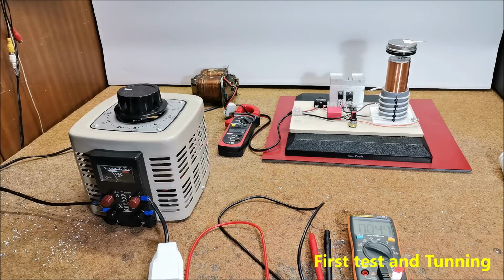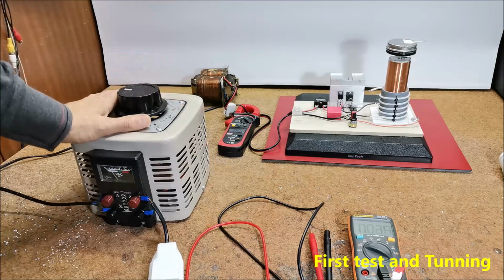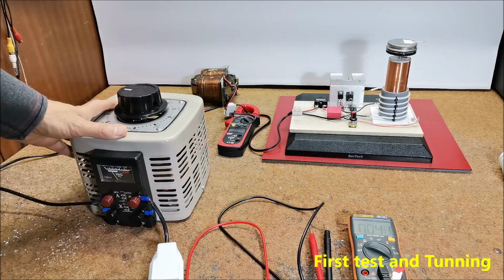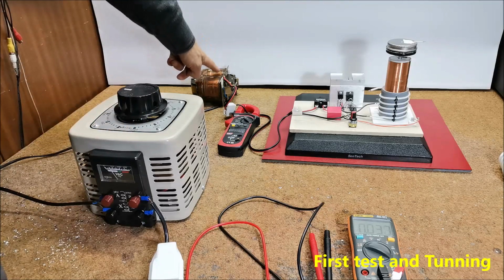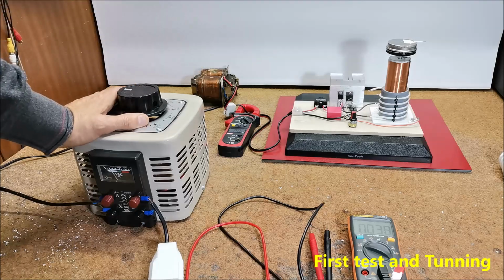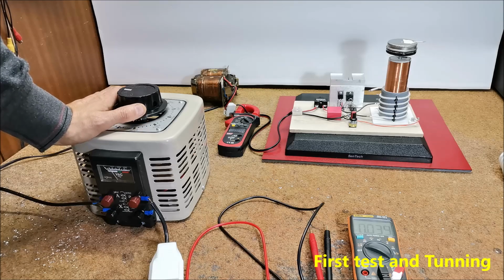If we do not have a variac auto transformer, it is best to start the test with a transformer with an output voltage of about 12 to 15 volts. When we solve the problem, we can start increasing the voltage continuously while keeping an eye on the current clamp.